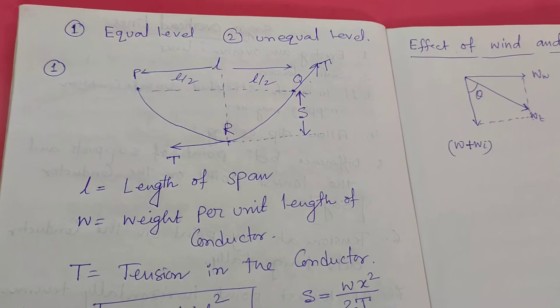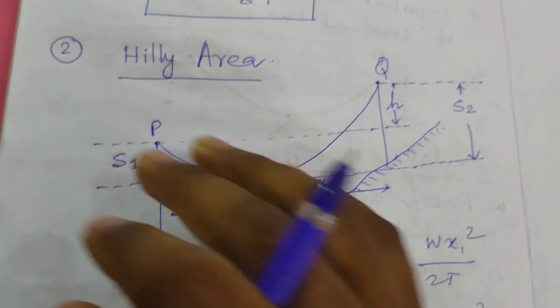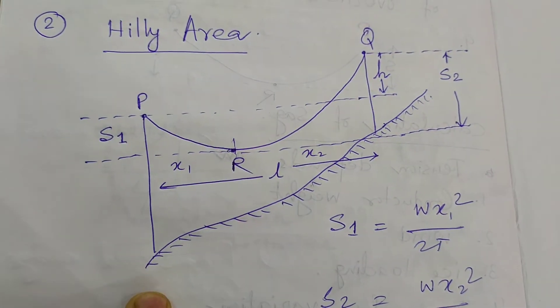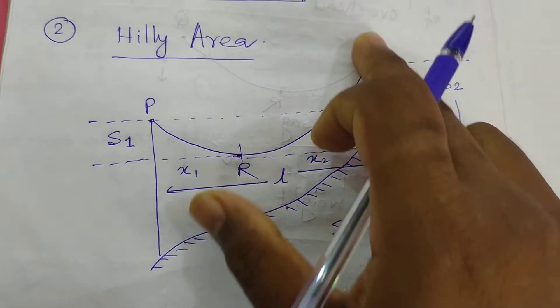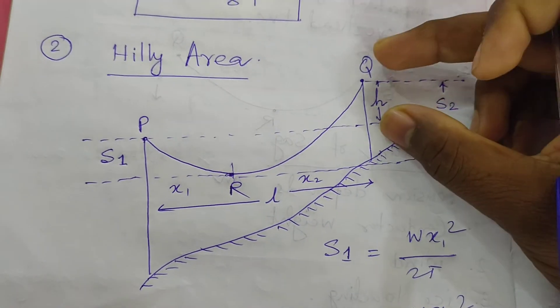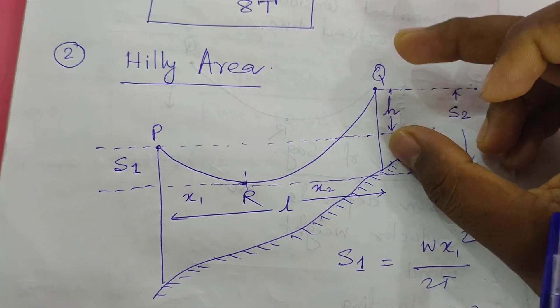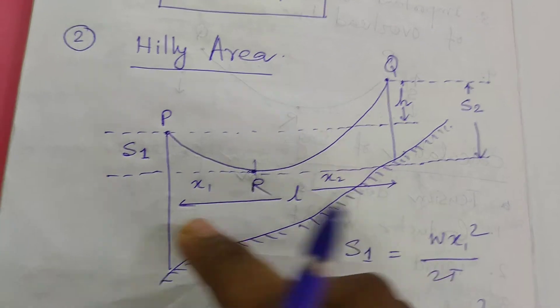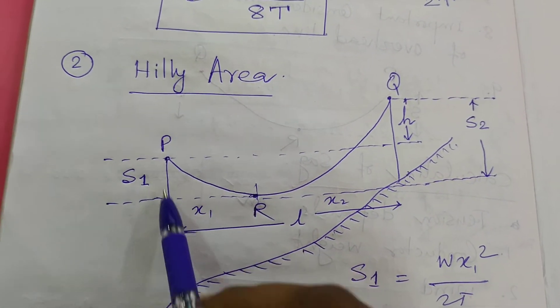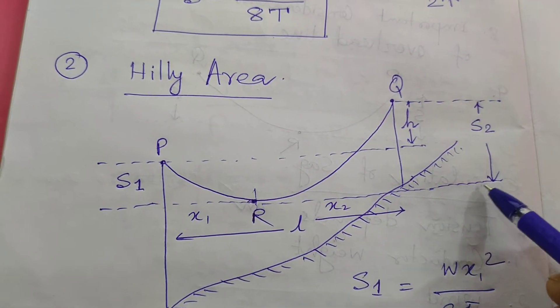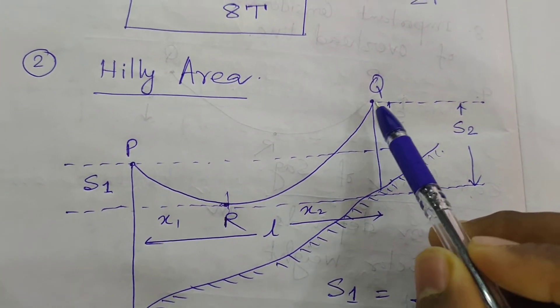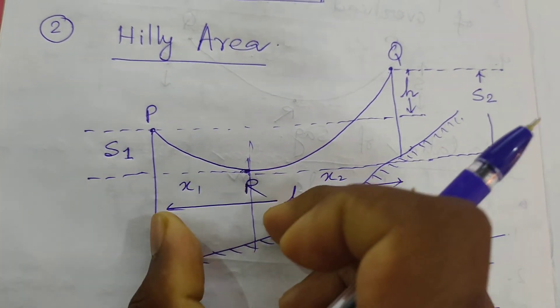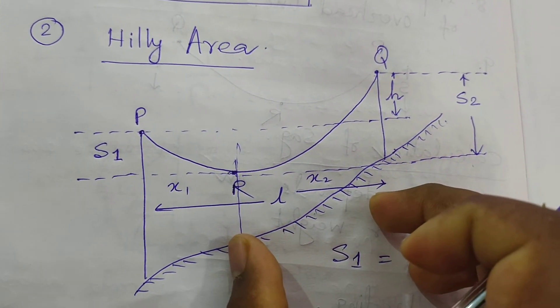For unequal distribution — unequal level — that is only applicable for the hilly area, as shown in this picture. This is the surface of the hill, and P and Q are the points where the transmission towers are located. The level is not equal. The difference between the support levels is H. H is the height difference between the equal and unequal support points, where R is the lowest point of the conductor. S1 is the SAG of the lower level tower, and S2 is the SAG of the upper level tower. X1 is the distance from the lowest point, and X2 is the distance from the highest point. L is the total span length.